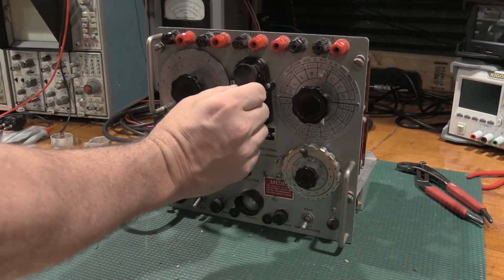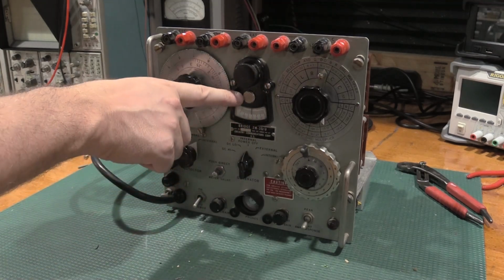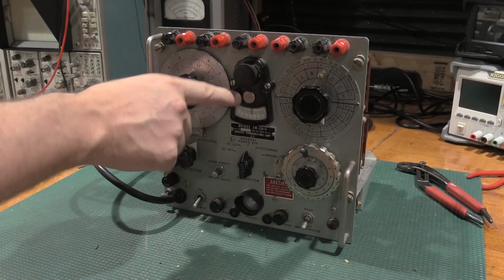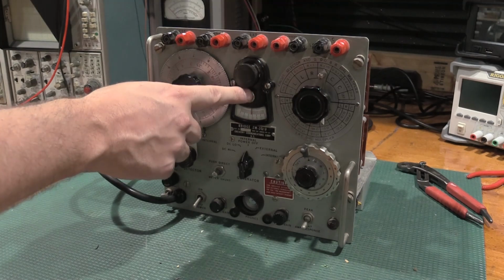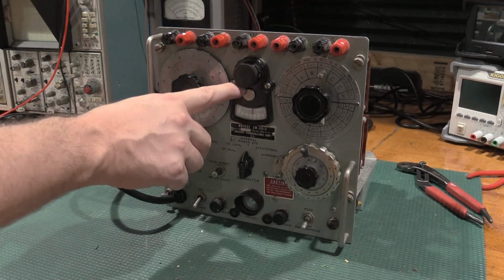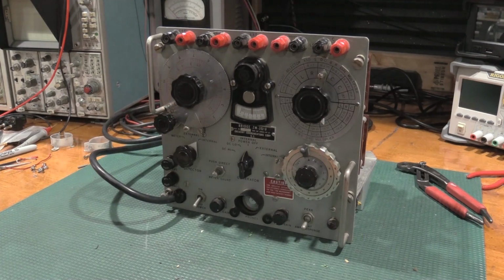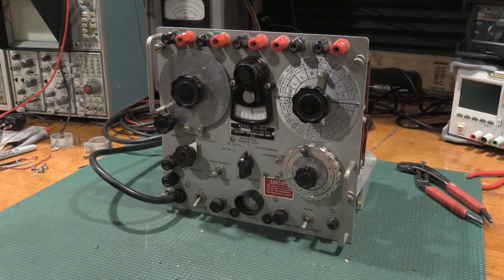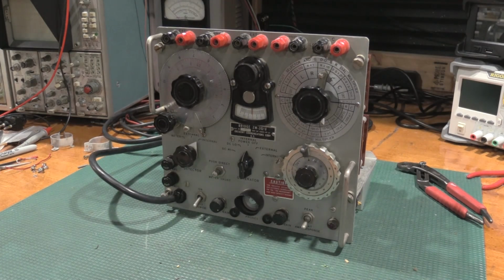Before we do anything, we're going to move the meter out of lock mode. This pin or not button right here slides up and down, and that locks the meter for transit, and this needs to be out of lock mode before we apply power so it doesn't bend the meter motion.